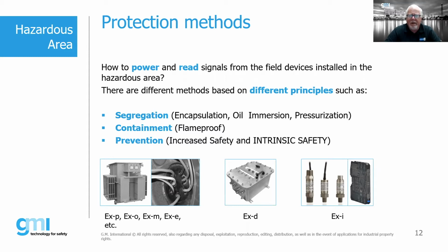Prevention. Prevention is basically increased safety and intrinsic safety. Prevention is saying, look, we're not going to have an arc or spark, or we're not going to have enough energy in this circuit to potentially ignite the flammable gas-air mixture. With increased safety, we do that by increased creepage and clearance requirements, making sure that there's no potential arcing. With intrinsic safety, we're limiting the amount of energy. So these are all the concepts that are commonly used, and again, these are just a handful of the most common ones. Other protection concepts are available as well.